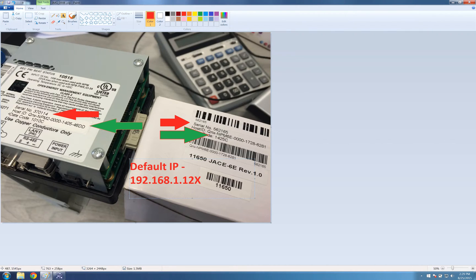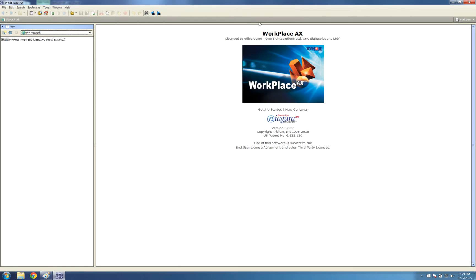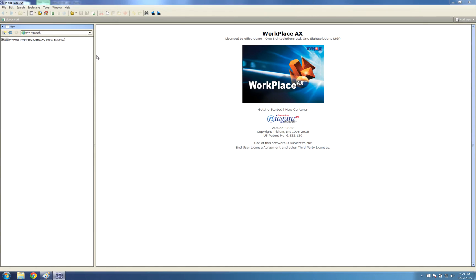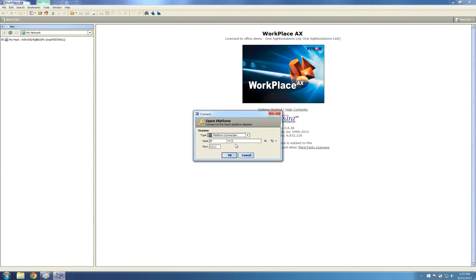So I will go over to the Niagara system here. I will punch in the IP address. I will go to File, Open, Platform. Now my serial number of this JACE ends in a 9, so I will go 192.168.1.129.